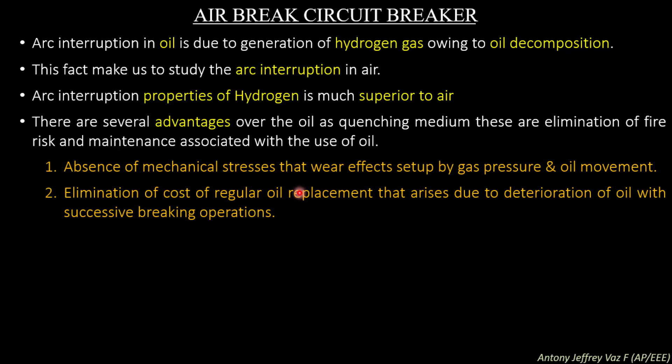Another advantage is the elimination of the cost of regular oil replacement arising due to deterioration of oil with successive breaking operations. The oil in an oil circuit breaker deteriorates because of decomposition due to the high temperature caused by the arc, and ionization of oil also takes place. Once the oil is ionized, it gets decomposed and this decomposed oil remains inside the circuit breaker. The waste ionized oil has to be removed and the breaker refilled with new oil of greater dielectric strength, making replacement costs higher than for an air circuit breaker.